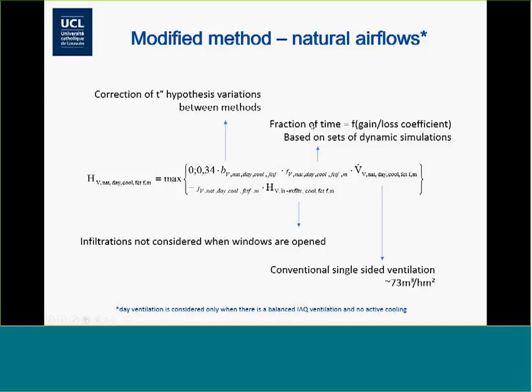Some factors, obviously, take into consideration the fraction of time, of how much time this ventilation will be used. It's a function of the gain-loss coefficient. It's something we also have in ISO norms. Nothing very specific about that. And a correction factor to consider the differences between the hypothesis we made in this static calculation and the dynamic simulations we do to evaluate coefficients such as the fraction of time. In fact, the correlation between the fraction of time and the gain-loss coefficient is set based on large sets of dynamic simulations, and there are some hypothesis discrepancies between the work done for those simulations and the hypothesis of the static calculation. So this coefficient is there to take that into account.